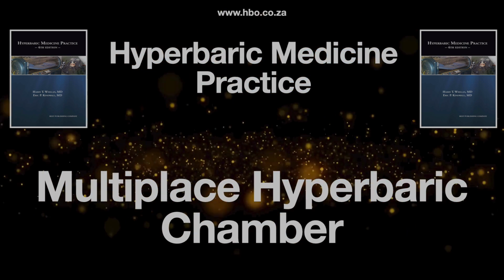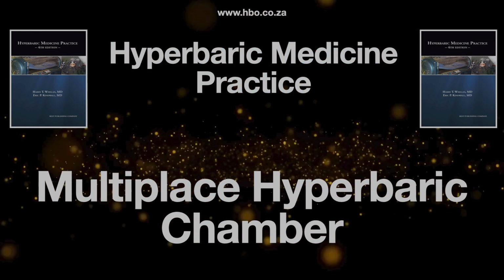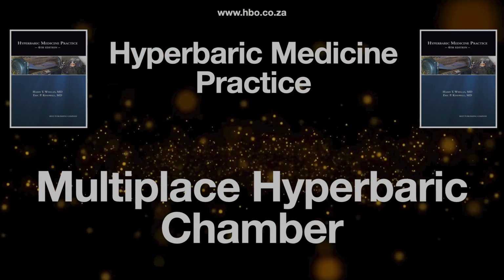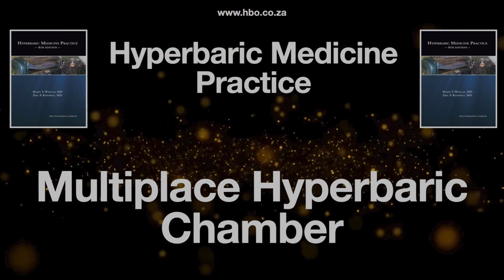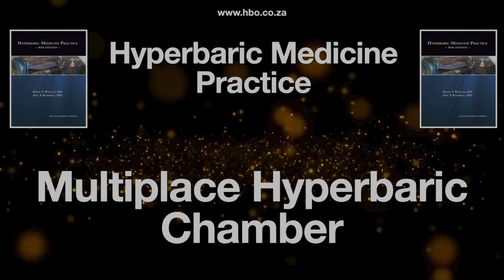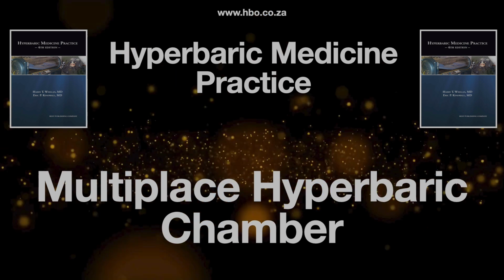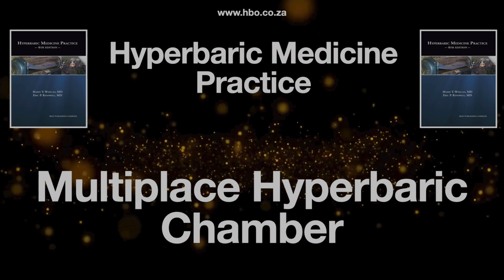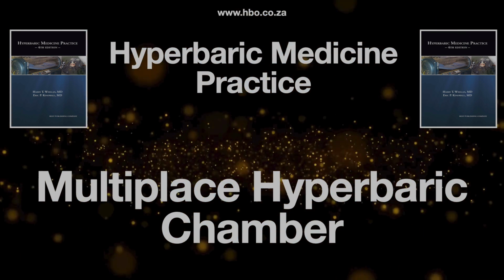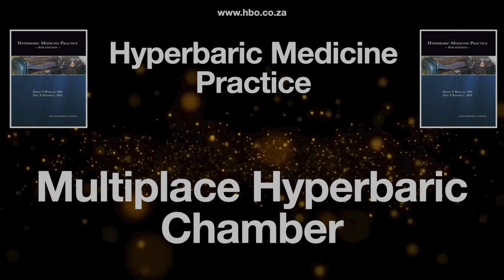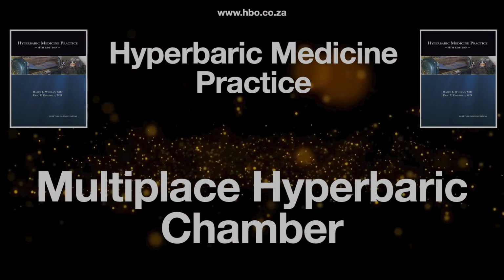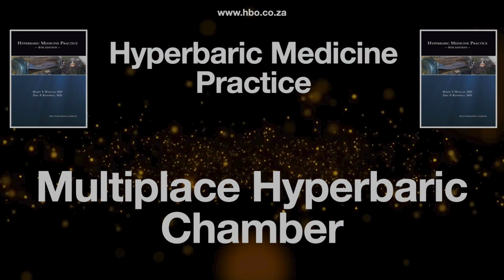Got it. And the ventilators. Equally critical if a patient needs breathing support. These aren't standard ventilators. They have to deliver steady gas flow, keep a constant breathing rate despite the big pressure swings. Right, the changing density of the air must affect things. Exactly. They also need various ventilation modes, VCV, SIMV, PCV, pressure support, plus PEEP settings. And you guessed it, enough battery power.